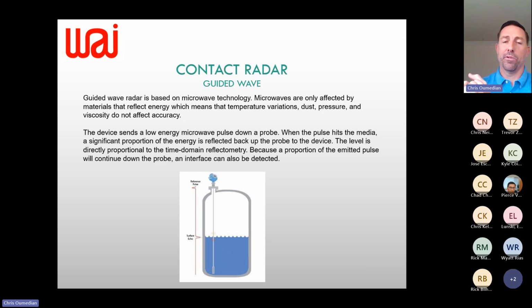The premise is the same as before — you're sending a wave out and back — but now using a probe. It's called guided wave because you're guiding that wave down the probe, which is contained within it, and it bounces the signal back based on where the liquid level is. The probe runs the depth of the tank, and the wave bounces off wherever the liquid or media sits within it. As the level goes up and down, signals return faster or slower depending on the distance, giving you that analog output.